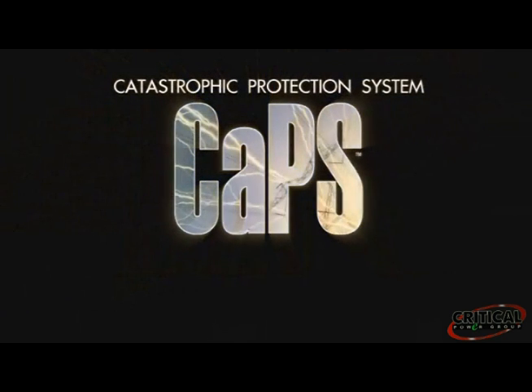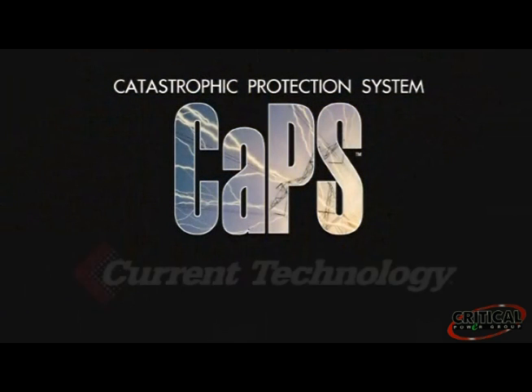Remember, not all overvoltage events are created equal. Temporary overvoltage or sustained overvoltage events can be just as destructive as a lightning strike. MOVs are great for transient surge protection, but TOVs and sustained overvoltage events can and do happen in the real world. And a better TOV solution is available. CAPS, the Catastrophic Protection System, from Current Technology.